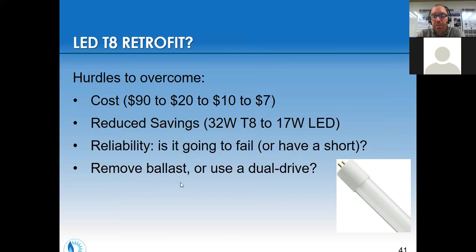If you remove the ballast, the fixture would just be getting line voltage. What happens if someone puts a T8 lamp back in its place? There are definite questions about keeping existing old fixtures with this potential for someone putting a fluorescent bulb back in. Some have a dual drive, able to run with or without a ballast, but then that ballast is just wasting energy and heating up, so it's probably not ideal either. Really, new fixtures is the ideal situation. Sometimes there are retrofits to existing fixtures that are DLC listed, DesignLights Consortium listed, but new fixtures is the way to go for LEDs at this time.